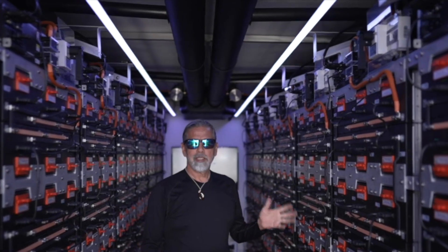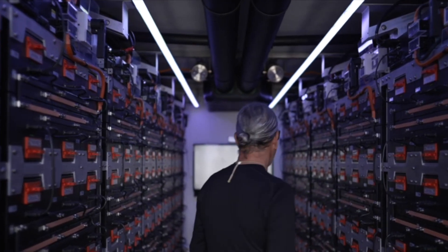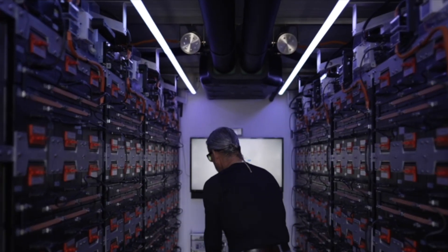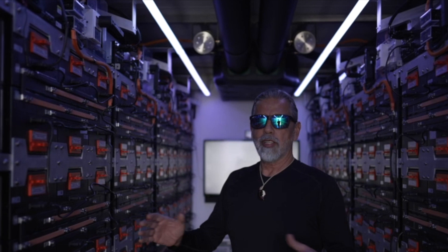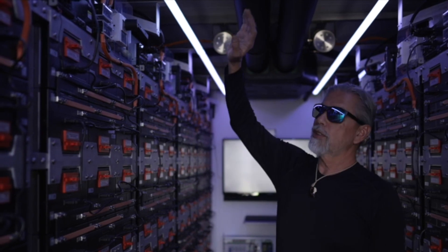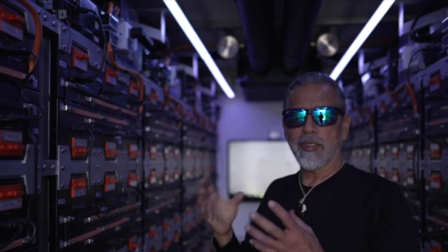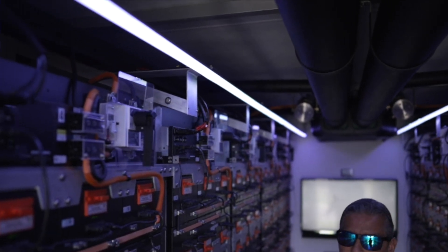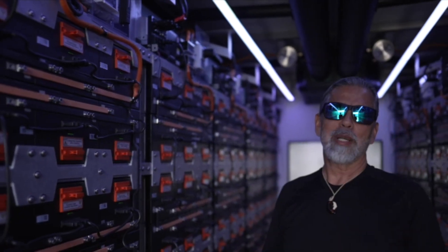So I showed you the HI and the LX — inside, 480 batteries, 2.2 kilowatt hours per module. The nice thing about lithium ferrous phosphate, which is our chemistry, is it doesn't get hot. So we basically don't need any cooling system for the batteries. We do have a cooling system, but it's for the electronics — electronics generate heat, so we need to keep them cool. If you're going to have a battery that gets hot, you're spending energy cooling the batteries, so that's a waste of energy.